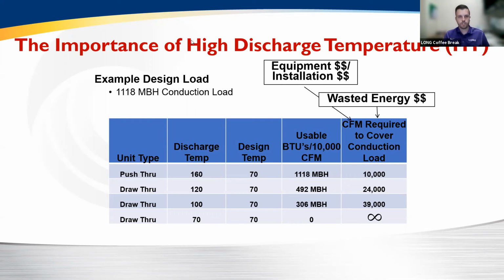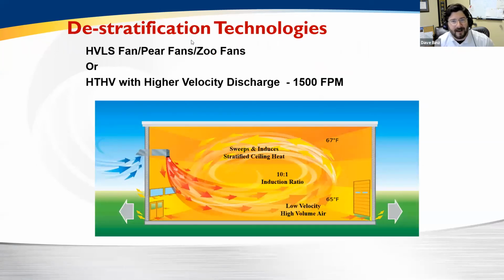Are there any concerns we should be aware of with respect to code requirements or stratification? Yeah, there's no restrictions from a code requirement. These technologies are all zero clearance to combustibles. And really what allows us to meet those two key concerns is our high velocity. So yes, we are discharging 160 degrees at the space, which can create quite a buoyant effect if you don't have destratification technologies. In many large warehouses, they use Pear fans, zoo fans, HVLS fans.